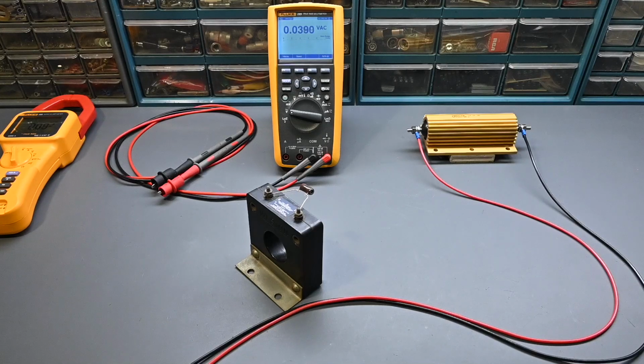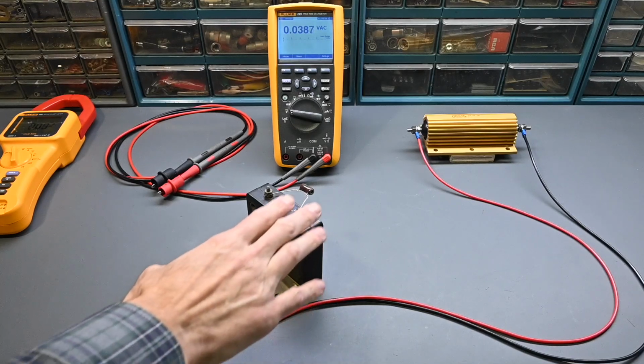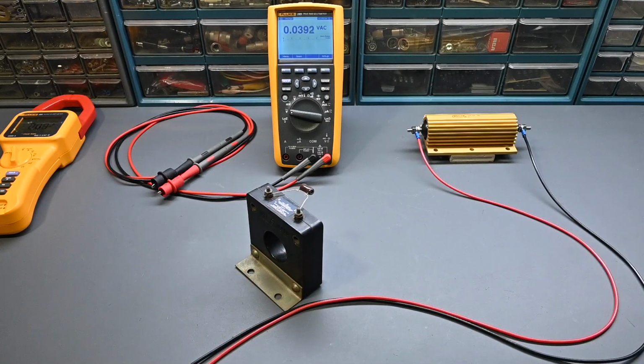So as the last example of a way to measure current, let's take a look at the current transformer. Now, I already mentioned that some current clamps are based on the current transformer principle, but let's take a closer look and see how this device actually functions. So a current transformer operates on the principle of sensing the magnetic field around a conductor, and they can only measure AC current. You cannot measure DC current with a current transformer. And of course, the frequency of the AC current must be within the range of the transformer.